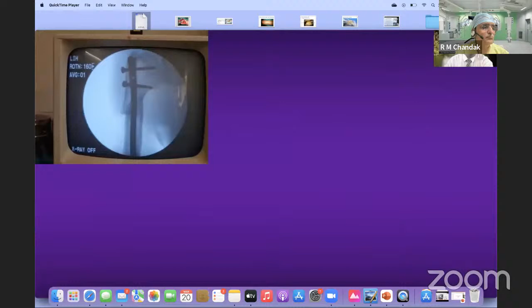Here is an example. Average is 1. This is the picture. 1 picture is taken and the image is displayed. 2 pictures are taken and 1 image is displayed. Average of 4, average of 8, average of 16. You can see that by increasing the average in a still part, the quality of the image doesn't improve. Only when you're using it for a chest, or probably when the patient is respirating while you're using it for spine, you can use a higher average.